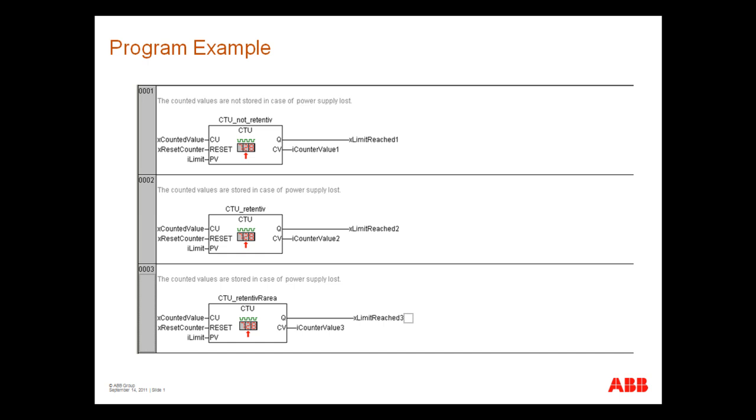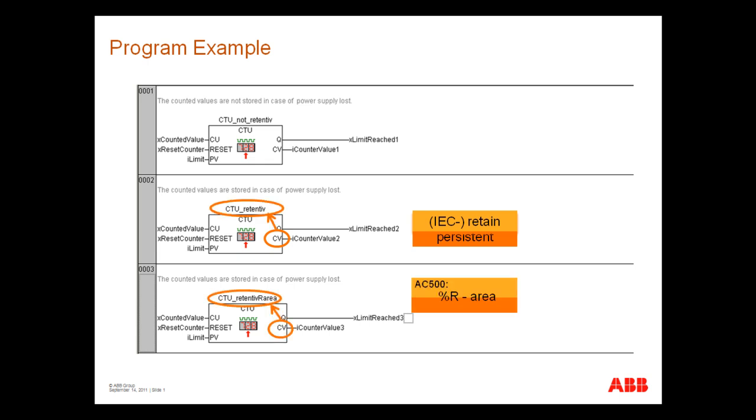To explain the declaration and behavior of the retentive variables, we will use a small project. This project contains 3 independent up counters. We will test the different behavior of the counters depending on the declared variable types. They will count the same pulses and can be reset by the same variable. For the second and third of them, the counted value should be buffered by program download and by lost power supply. In this case, to keep the value, the counter instance is to be buffered.